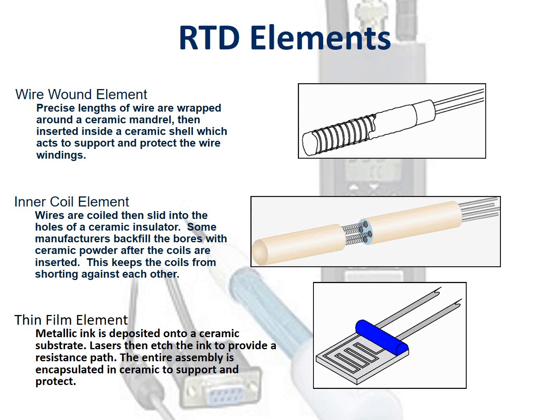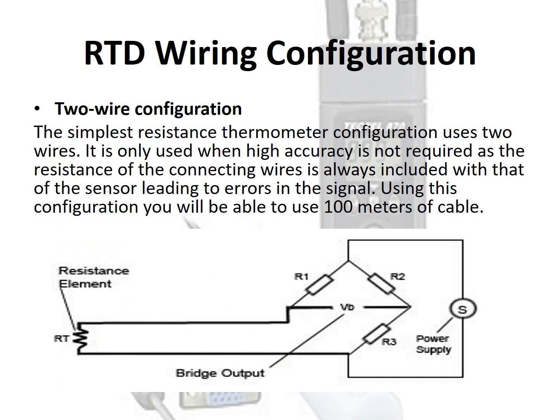The simplest resistance thermometer configuration uses two wires. It is only used when high accuracy is not required, as the resistance of the connecting wires is always included with that of the sensor, leading to errors in the signal. Using this configuration, you will be able to use 100 meters of cable.